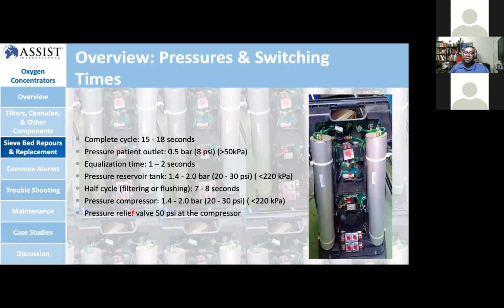After you complete all the tests, install back your zeolite, and you need to check the patient outlet pressure, about 8 PSI. And equalizer time, 1 to 2 seconds. The equalizer valve should change to 2 seconds. Then the reservoir tank pressure should be 20 to 30 PSI. And the half cycle on the high pressure should be 7 to 8 seconds.